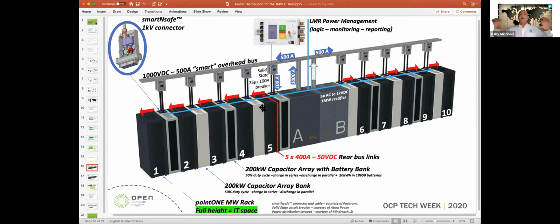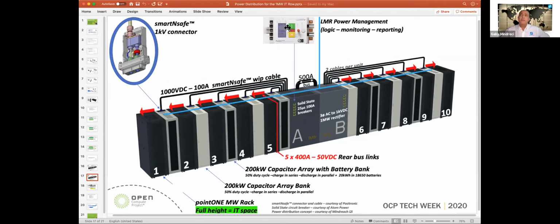It is a challenge, but these bus links would be standard. They can be configured to be plug and play at each level, whatever the level may be. Five of them will be sufficient to distribute the power accordingly on the rear of the rack. With a similar situation, when we're looking at the solid state breaker, we were working on solid state breaker technology with companies such as Atom Power. This image is courtesy of Atom Power, and they have pretty advanced development with breaker points at around 100 amps. So it can be set objectively to trigger a disconnect at 110 amps, let's say, rather than a larger spectrum with the conventional type breakers.